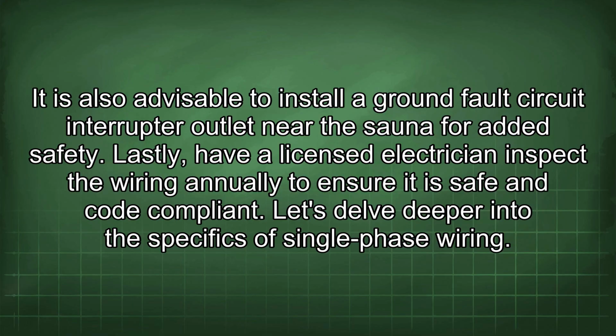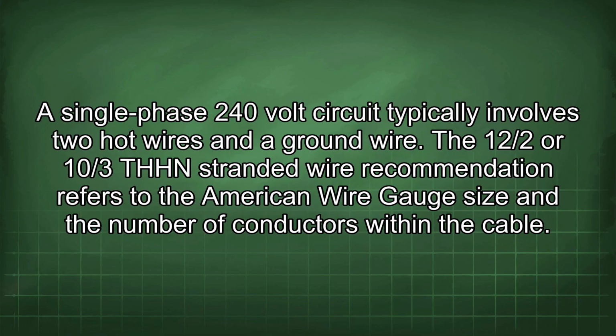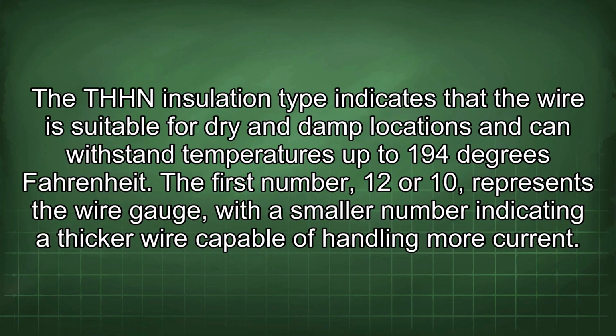Let's delve deeper into the specifics of single-phase wiring. A single-phase 240 volt circuit typically involves two hot wires and a ground wire. The 12/2 or 10/3 THHN stranded wire recommendation refers to the American wire gauge size and the number of conductors within the cable. The THHN insulation type indicates that the wire is suitable for dry and damp locations and can withstand temperatures up to 194 degrees Fahrenheit.